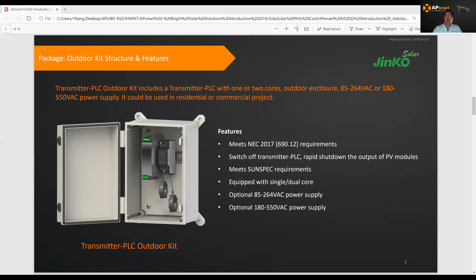there are 2 CT along with that. Actually, I can show you that here. And see. Yeah, so on the bottom you have the screen, and this is the CT, so you can just screw in there to make the connections. Each CT, they can go through 10 strings. Each string, you can go up to 30 PV modules, which means each CT, you can go up to 300 PV modules. Our transmitter allows the maximum 2 CT in one device. So the maximum would be 600 PV modules when you design your system.